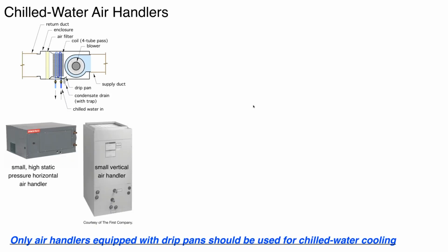All right, let's talk about terminal units, specifically air handlers. In small scale systems, there are a variety of air handlers available. They're usually categorized as either horizontal or vertical. There are some products on the market now that can convert between vertical or horizontal, depending on what the application is. Basically, it would change the orientation of the coil inside the cabinet.